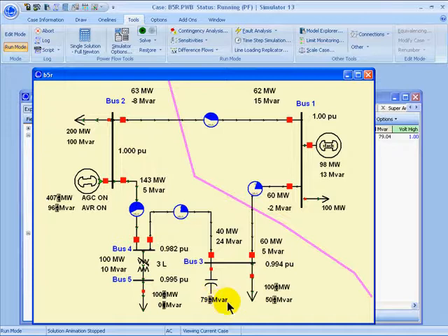The nominal megavars are the 80 megavars, which are derived from the 4 blocks of 20 that were specified. The reason why the 79 is a little bit lower is because the actual megavar is dependent on the square of the terminal voltage.